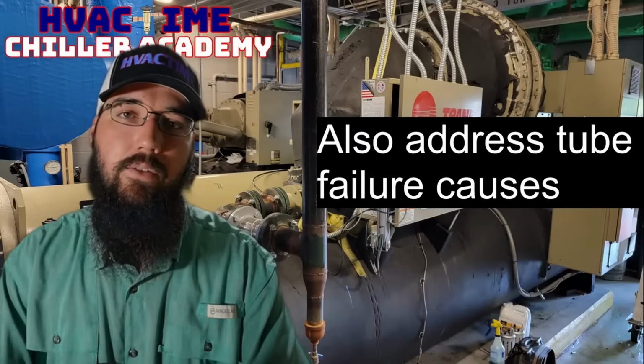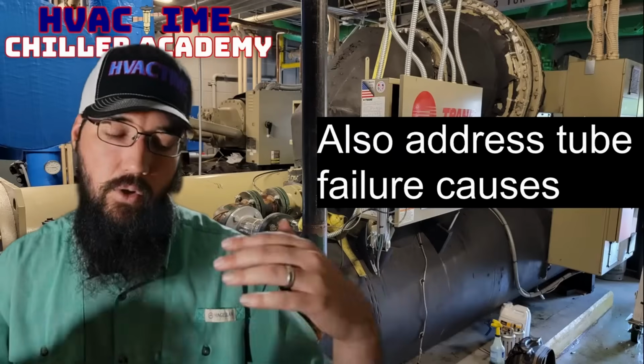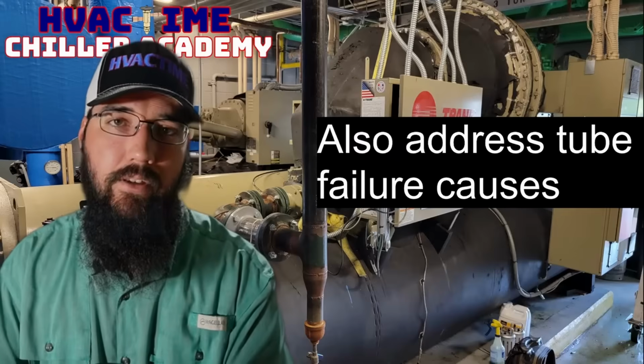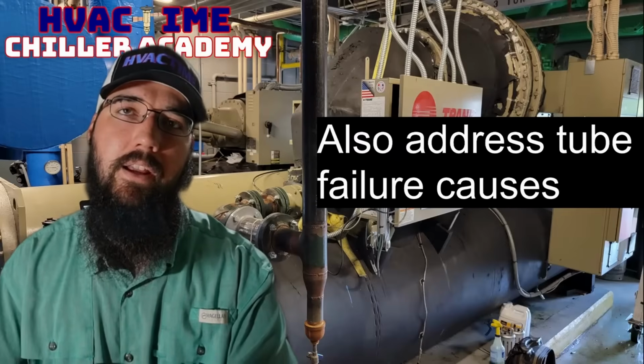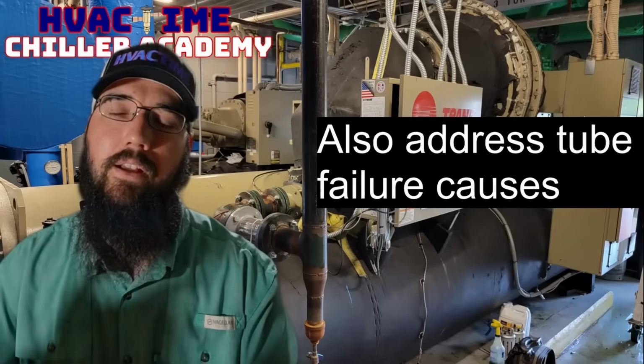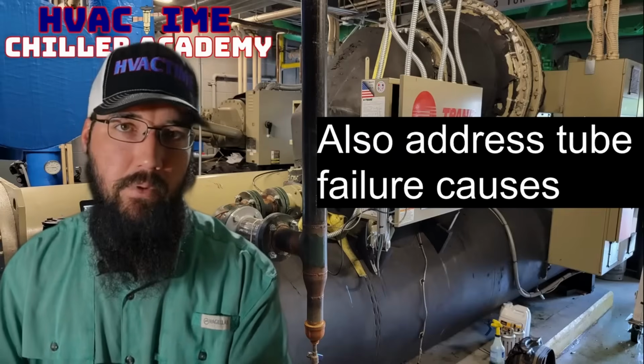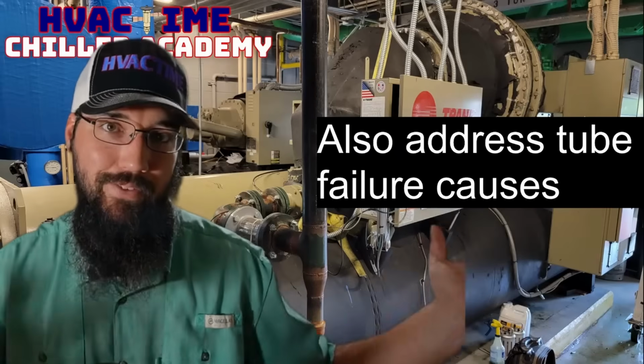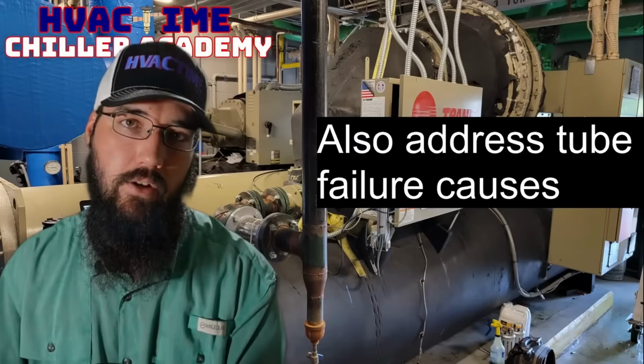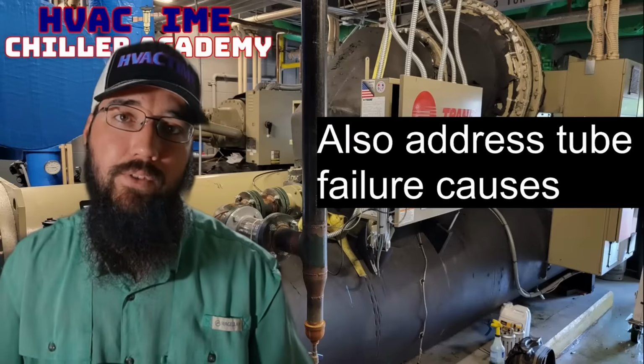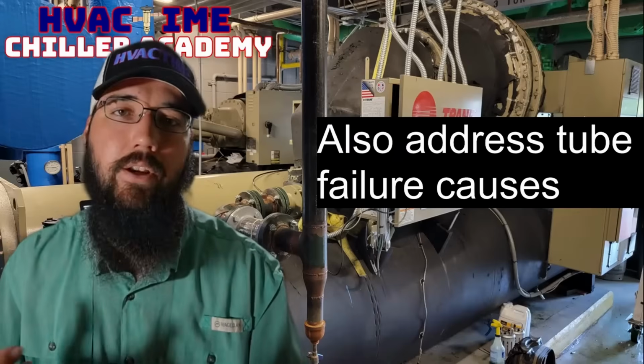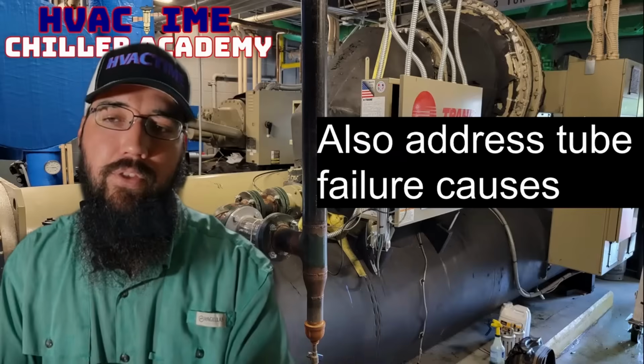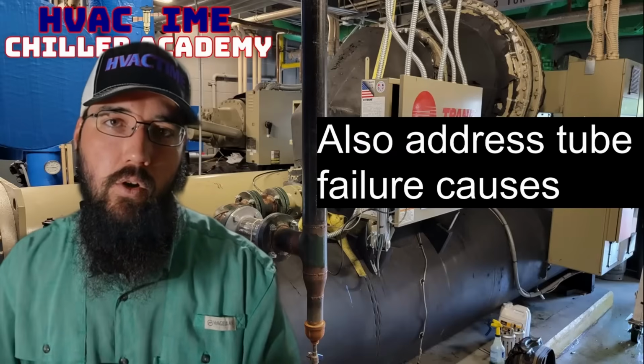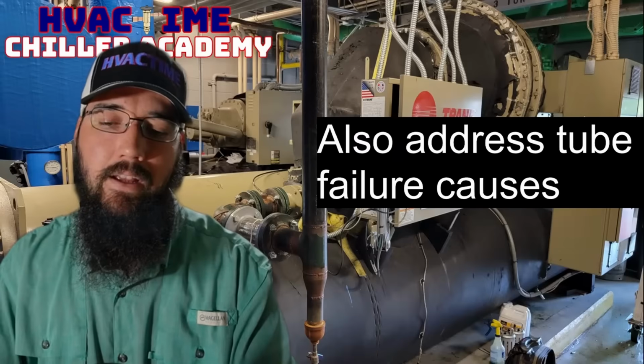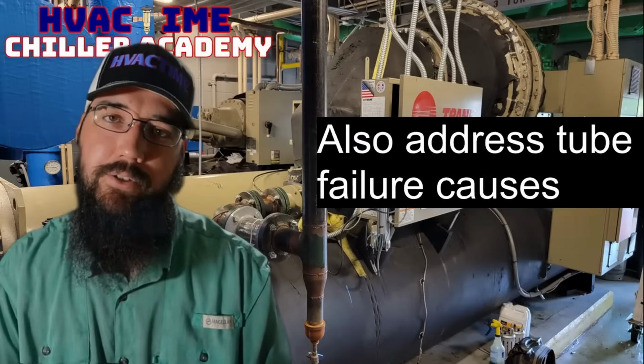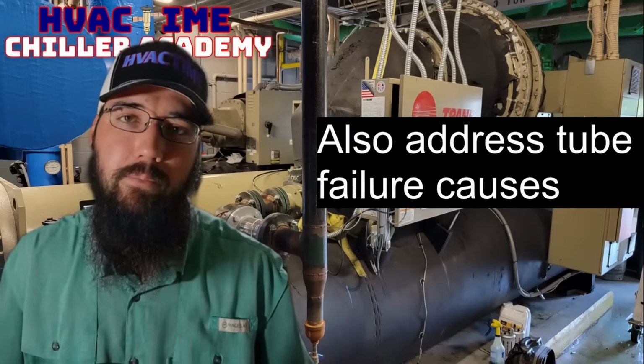There are a few ways to go about why the tube has failed. You could have general erosion. If you've got a system with a lot of heavy debris flowing through it, whether that be mud, silt, or other parts from the system, that can put a lot of extra wear on the tubing itself. It's also going to mean you're having to brush those tubes far more often, and brushing the tubes creates more wear. As more wear is added, you thin the wall of the tube, and eventually the tube wall can get so thin that it can't hold up to the refrigerant pressure and the water pressure anymore, and a leak ends up forming.